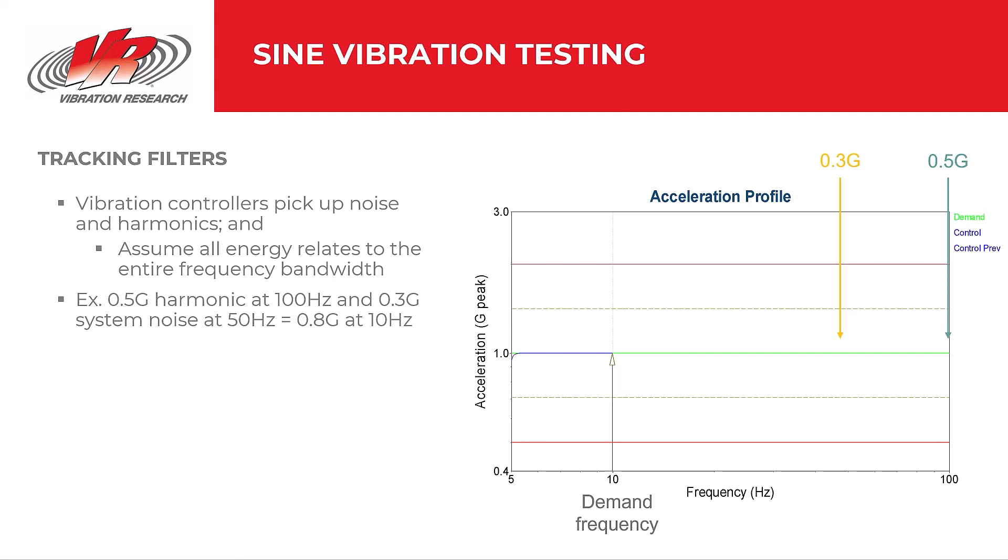Now, this is an oversimplification because the controller doesn't just add all the acceleration together, but instead calculates an average RMS. However, those noise and harmonics do contribute to the average RMS and can affect the drive.